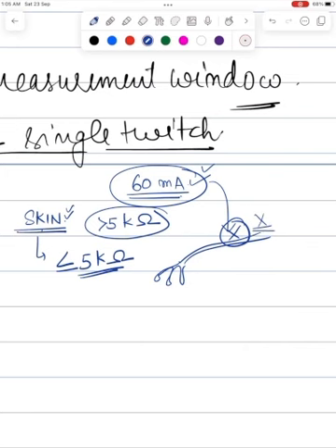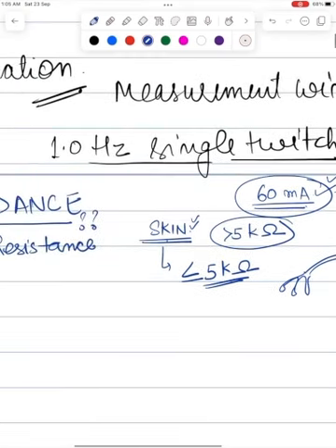milliamperes of current. In fact, the whole reason of using a supramaximal stimulus is actually to overcome this electrical resistance of the skin, so as to get a response every time despite changes in skin resistance. However, certain newer devices measure and indicate the level of skin resistance on the screen, and in such cases, establishment of a supramaximal stimulus is generally not needed.